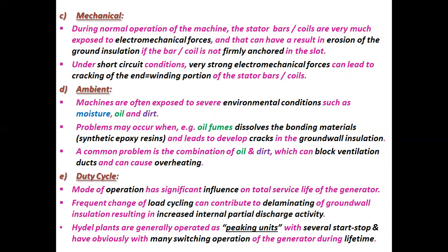D. Ambient. Machines are often exposed to severe environmental conditions such as moisture, oil, and dirt. Problems may occur when, for example, oil fumes dissolve the bonding materials, that is synthetic epoxy resins, and lead to the development of cracks in the ground wall insulation. A common problem is the combination of oil and dirt, which can block ventilation ducts and cause overheating.